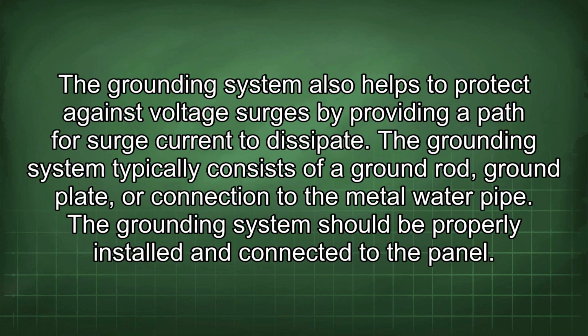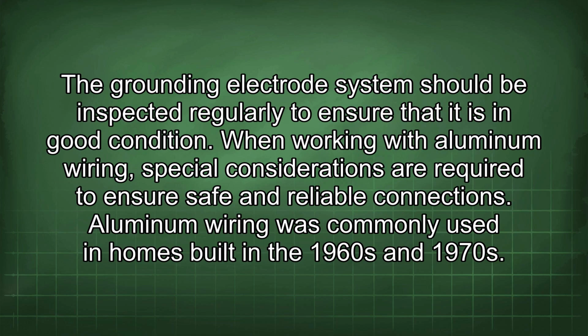The grounding system also helps to protect against voltage surges by providing a path for surge current to dissipate. The grounding system typically consists of a ground rod, ground plate, or connection to the metal water pipe. The grounding system should be properly installed and connected to the panel. The grounding electrode system should be inspected regularly to ensure that it is in good condition.